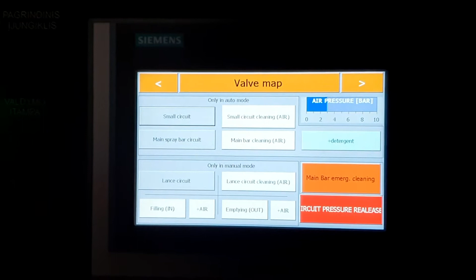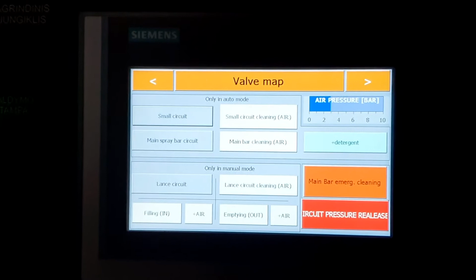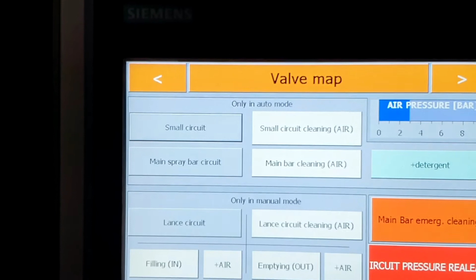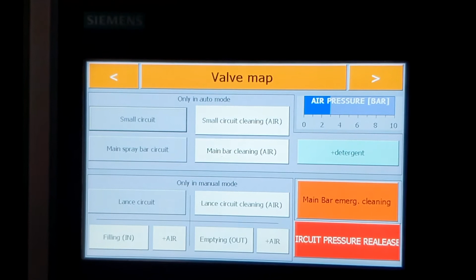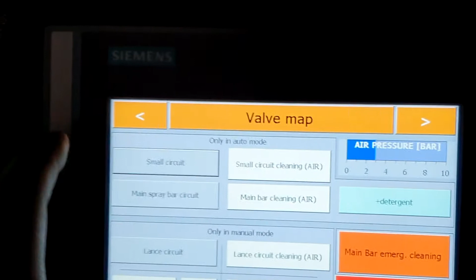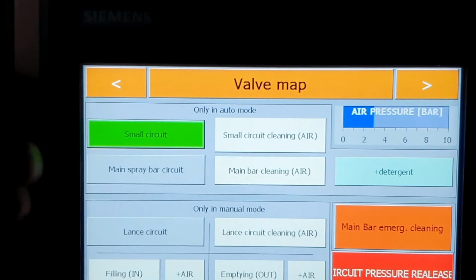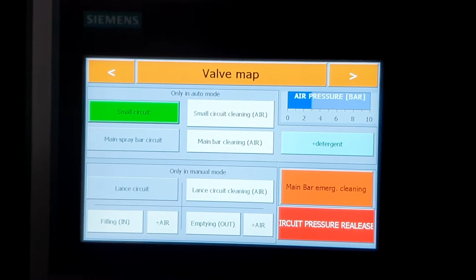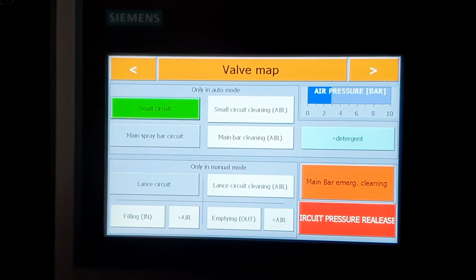And in the newest version, all of this is done automatically with the control of a PLC, and you only push the buttons correctly in order on this screen. So going from the top, we've got the small circuit circulation. This is for preheating of emulsion in the circuit of the spray bar later on. The first step would be to turn on the small circuit circulation. It will light green. Now we know that the pump is pumping and the valves are set up in a way that is the shortest way going through the pump, only for homogenization of the emulsion in the tank. So this is the mode which is used for heating up the emulsion before we go to the spray bar circuit and effectively into spraying mode.